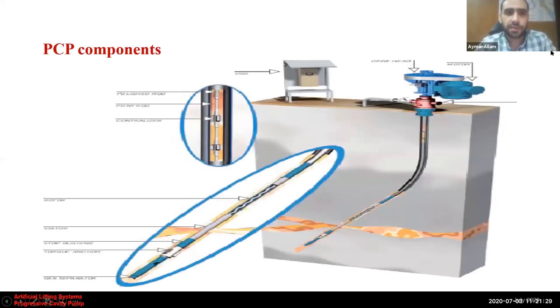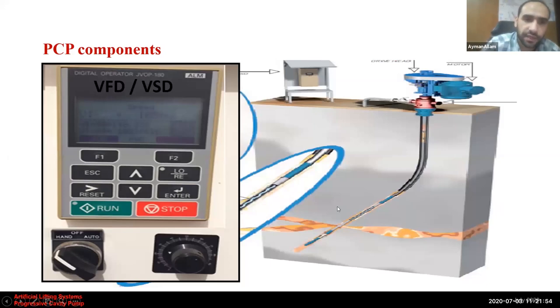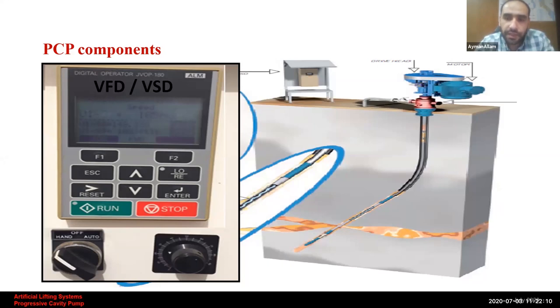Now let's go through the PCP components, classified as surface components and downhole components. Starting with surface components: number one is the electric panel, also known as VFDs or VSDs — Variable Frequency Drives. The function of the electric panel is to protect the motor against any power source disturbance, provide power consumption optimization, and enable control of the motor speed and consequently the pumping speed.